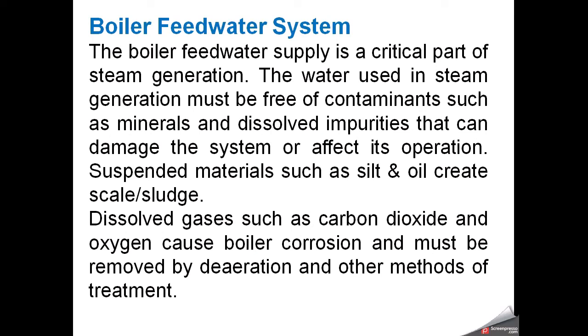The boiler feed water system supplies pure water for steam generation. The water used must be as pure as possible, with minimal dissolved impurities, minerals, sludge, or suspended particles. Increased impurities cause scaling, sludge formation, and corrosion in the boiler system. Dissolved gases must also be removed to avoid corrosion. Water passes through a reverse osmosis membrane or water treatment plant before becoming boiler feed water, and deaerators are present to remove dissolved gases.